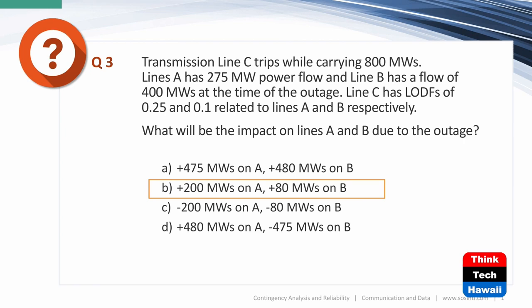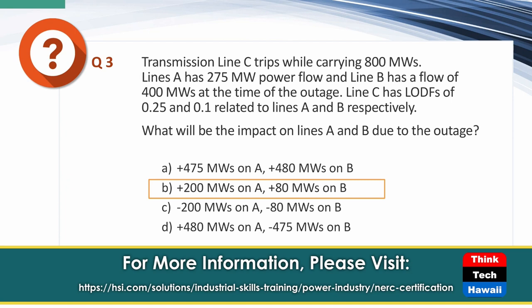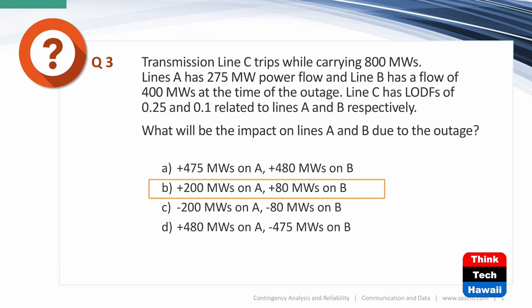Let's start on the first set of slides. Here's an example: Transmission line C trips while carrying 800 megawatts. Line A has 275 MW of power flow, line B has a flow of 400 MW at the time of the outage. Line C has a Line Outage Distribution Factor of 0.25 for line A and 0.1 for line B. The answer is 200 MW on A and 80 MW on B — simply multiply 800 by 0.25 to get 200, and 800 by 0.1 to get 80.